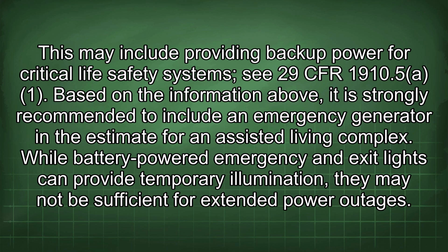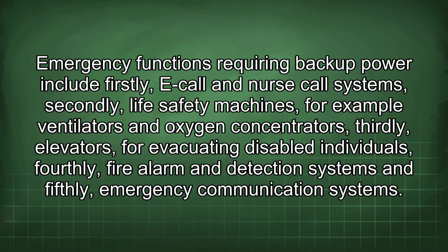Based on the information above, it is strongly recommended to include an emergency generator in the estimate for an assisted living complex. While battery-powered emergency and exit lights can provide temporary illumination, they may not be sufficient for extended power outages. Emergency functions requiring backup power include, firstly, e-call and nurse call systems; secondly, life safety machines, for example ventilators and oxygen concentrators; thirdly, elevators, for evacuating disabled individuals; fourthly, fire alarm and detection systems; and fifthly, emergency communication systems.